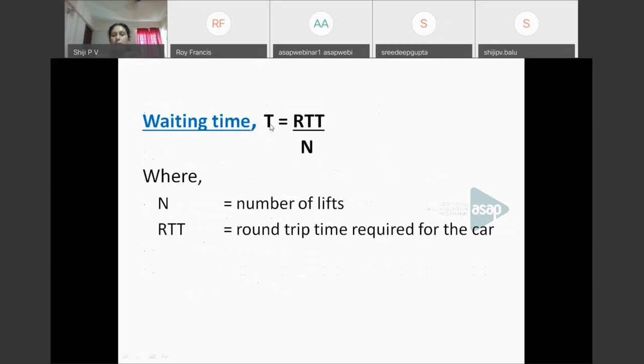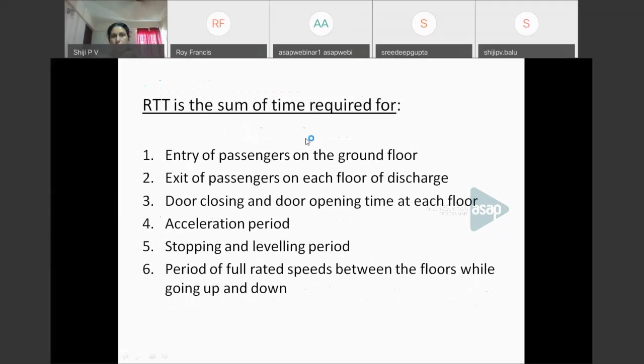Now, what is round trip time? The round trip time is the time required by a lift during its full motion, that means during ascending as well as descending. It includes the door opening time, closing time, entry of passengers at the ground floor, exit of passengers at the different floors, then acceleration period, stopping time, and full speed motion period. All these times are added up to get the round trip time of a lift. That divided by the number of lifts will give you the waiting time in seconds. This waiting time can be used to calculate the handling capacity of the lift.